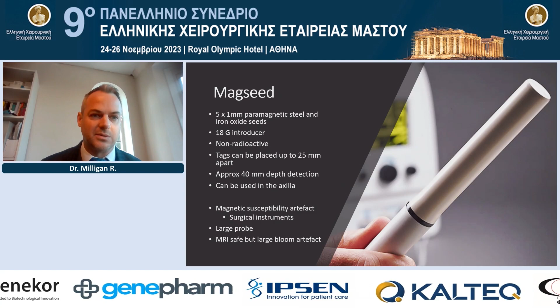The induced magnetism from the probe means that any iron-based instruments can disrupt the signal. So plastic surgical instruments are recommended, or no instruments and just fingers when using the probe. The probe itself is relatively large in comparison to the other alternatives on the market. MagSeed is safe, but there is a large bloom artifact, which you'll see with many of these devices. So here is a paper we wrote showing that MagSeed is a safe alternative to guide wires, showing good resection margins.